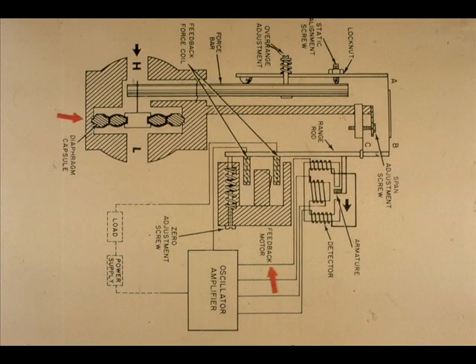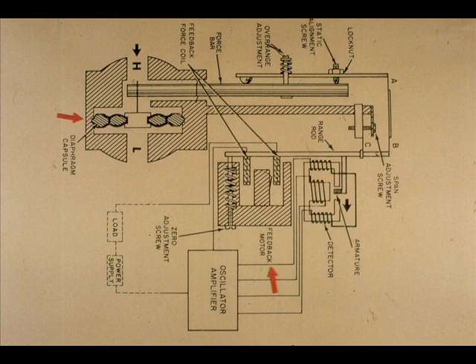The force developed by 10 to 50 mA DC through the feedback motor opposes the force across the capsule. The forces will balance within the range of the transmitter.